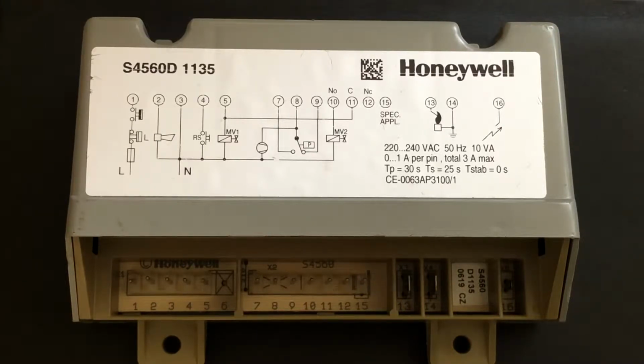Some people just put a wire between number 7 and 8 and want to simulate a pressure switch. That's not only illegal, to simulate the presence of a differential pressure switch, but the system will not work, because when the fan goes off, the differential pressure switch should go back to its normal position, a normally closed circuit between 8 and 9. Please don't make this mistake.